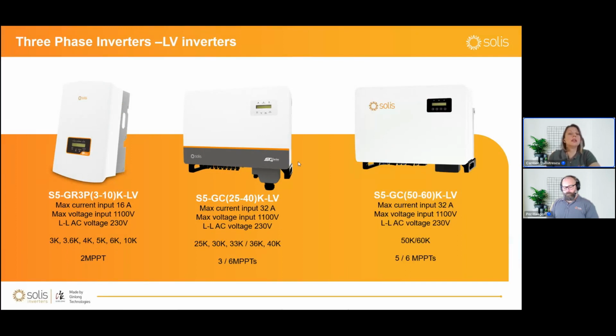Of course, I need to also mention the LV inverters from this product range. These are inverters which are dedicated for the Norwegian and Belgian market. These are the ones which are able to connect to the IT grids, where the voltage in between the phases is 230. We have the S5 from 3 up to 10 kilowatt. We also have the 25 to 40 kilowatt and the 50 and 60. All these, as you can see in their naming, at the end they have this LV, which stands for low voltage AC grids, and can only be used in these type of grids.